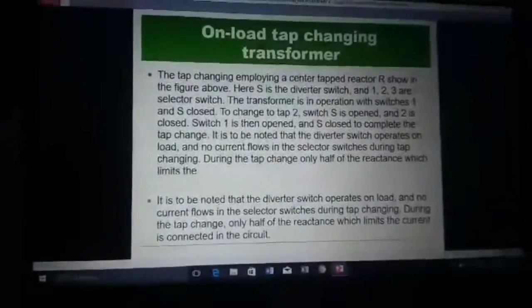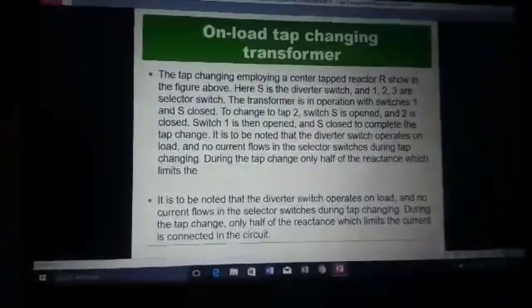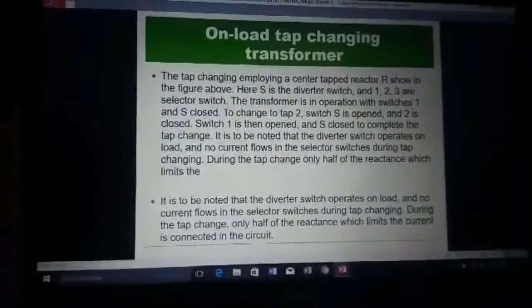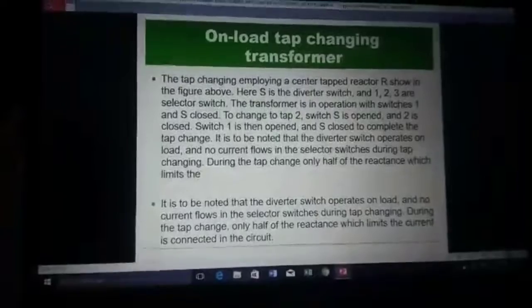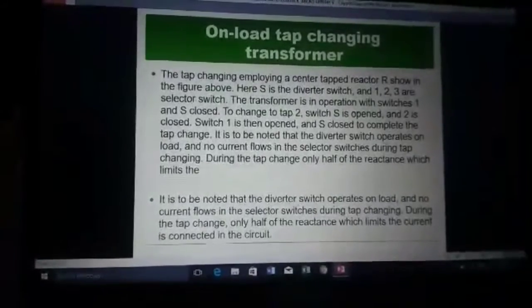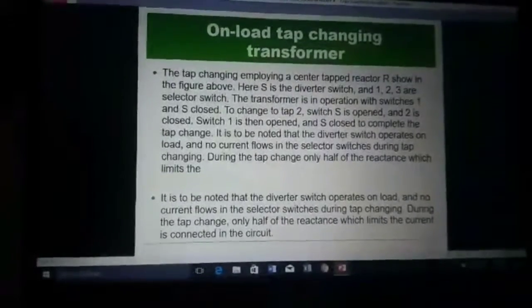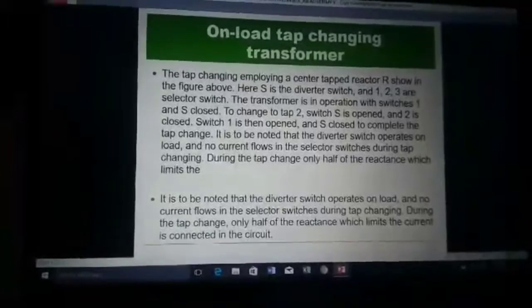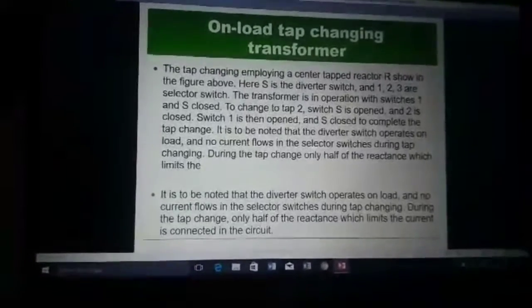The transformer is in operation with switches 1 and S closed. To change to tap 2, switch S is opened and 2 is closed. Switch 1 is then opened and S closed to complete the tap change.